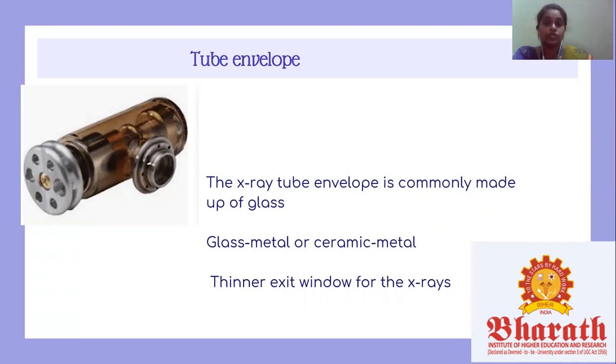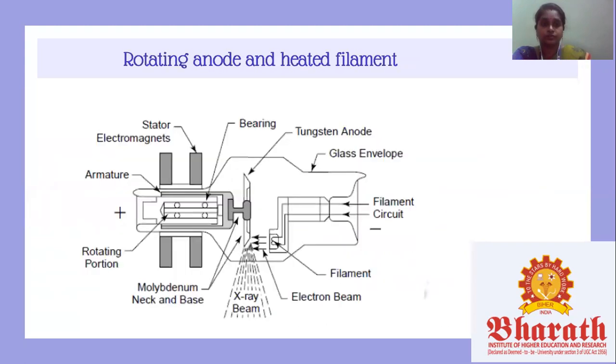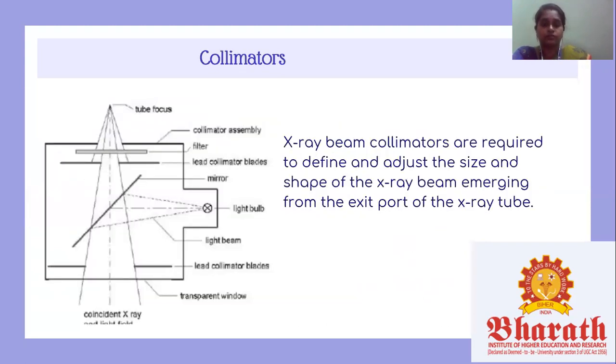the tube itself. X-ray production is a rather inefficient process, and much of the electrical energy goes on to be converted to heat. The design of the housing or the tube envelope incorporates an oil bath, cooling fans and so on. It also has leakage radiation, which the housing is designed to reduce to less than 100 mR per hour, and it requires regulation periodically.